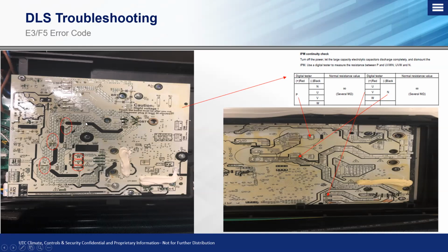Now, what you want to do is get out your electrical meter. You want to set it for megohm readings. If you have an auto ranging meter, then it will automatically set itself, or you have a manual option where you can force it into a specific reading that you're trying to take. What you'll do from there is take your red lead and put it on the positive terminal, and take your black lead and put it on the negative terminal. So you're just checking continuity between each capacitor bus. You want to verify that these capacitors are good and that they're allowing DC voltage to go not only to your outdoor fan motor, but to the compressor itself.